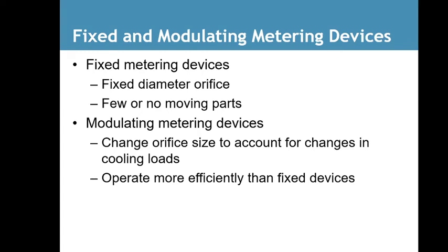Fixed and modulating metering devices. Fixed metering devices have a specific diameter of an orifice, and you can change that. So they have drill kits that you can buy for refrigeration orifices, and the same drill kits you use on gas orifices for gas appliances. You can change the diameter, or you can just buy or get one of the same size.